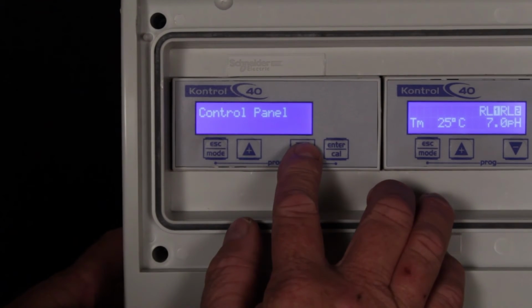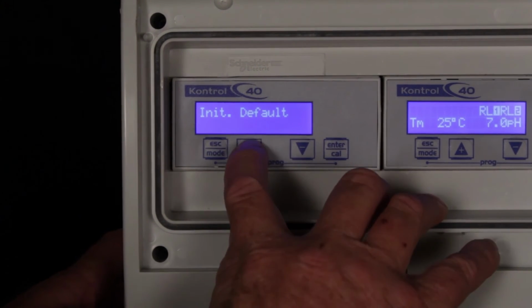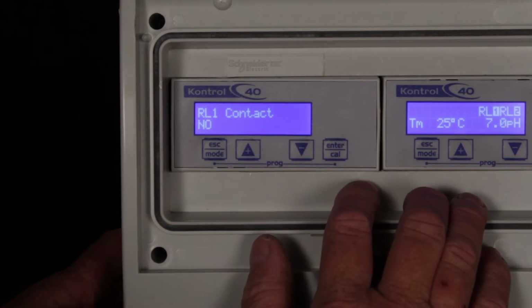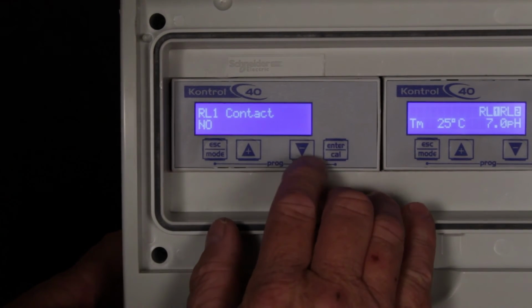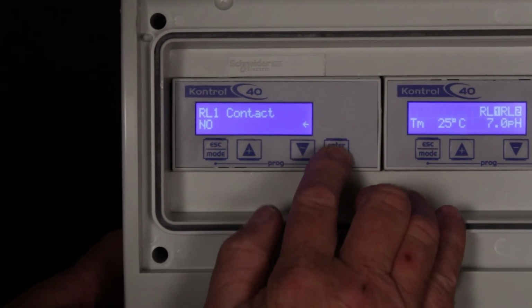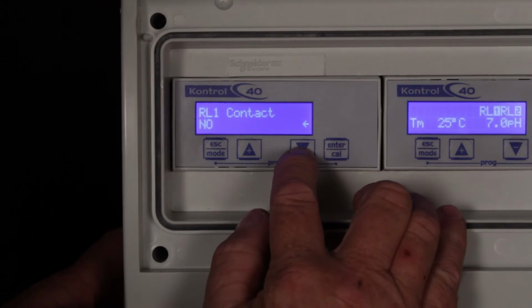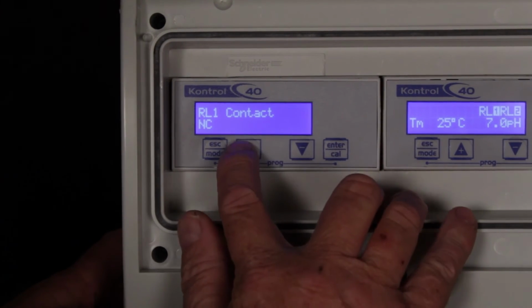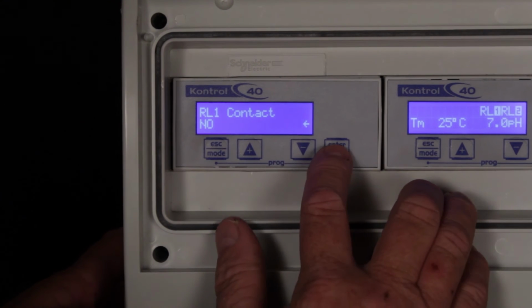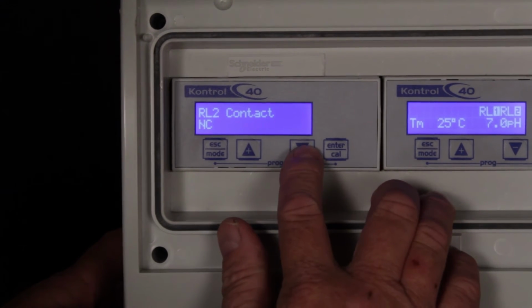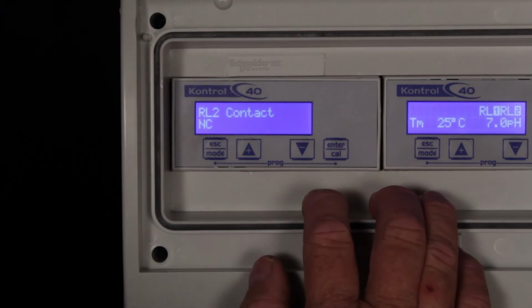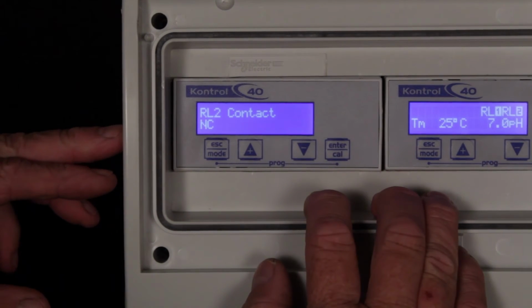For the relay setup, go to the control panel menu on the EC controller. Press enter to go to relay 1 contact. The default is set to normally open. To change, press enter, then with the up and down arrows, change it to the value required. For this application, we will need relay 1 as a normally open contact.